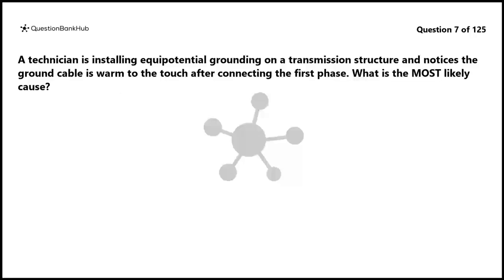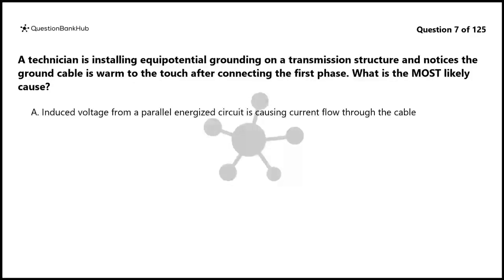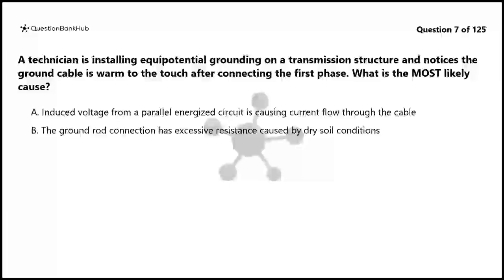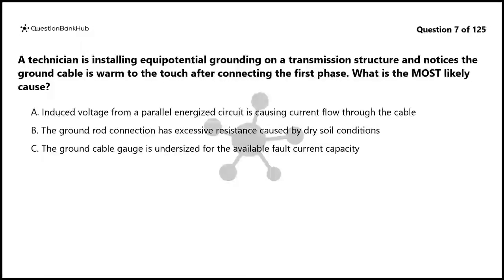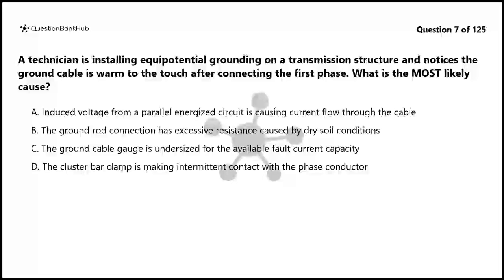Question 7. A technician is installing equipotential grounding on a transmission structure and notices the ground cable is warm to the touch after connecting the first phase. What is the most likely cause? A. Induced voltage from a parallel energized circuit is causing current flow through the cable. B. The ground rod connection has excessive resistance caused by dry soil conditions. C. The ground cable gauge is undersized for the available fault current capacity. D. The cluster bar clamp is making intermittent contact with the phase conductor.